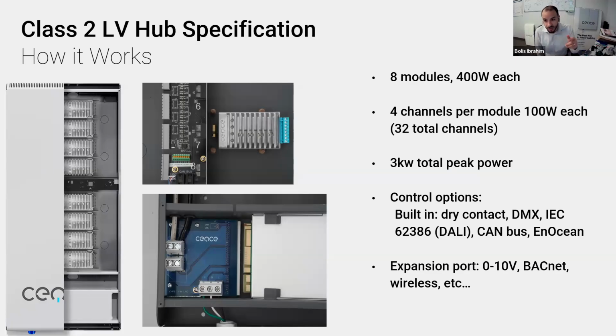Most manufacturers, for example, if it's PoE, power over Ethernet, that's a fixed voltage, I believe fixed at like 52 or 53. Most manufacturers will have different versions. The standard voltages in the market are 12 volts, although I wouldn't recommend 12 volts because the voltage drop is going to be such a great percentage. 24 volts is the most common, which is weird to me because the code allows you to go up to 60. So why would you do 24? But the industry majority is 24 volts. So yes, there's a 24 volt option. Our system is programmable, voltage and current is programmable, and you can set it up to 60. But we have common voltages, those are 24 volts. The majority of stuff out there is 24.